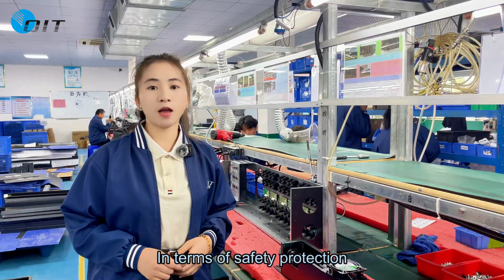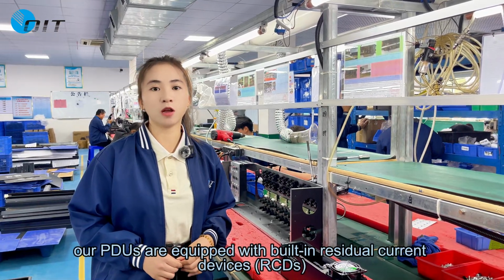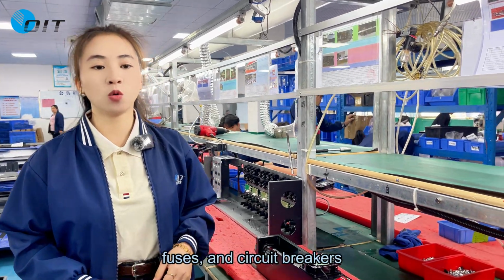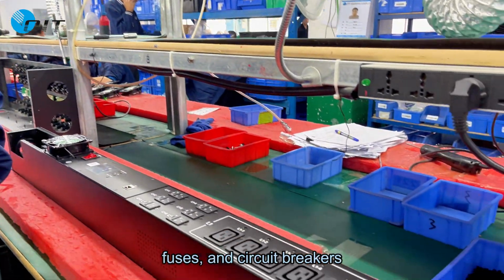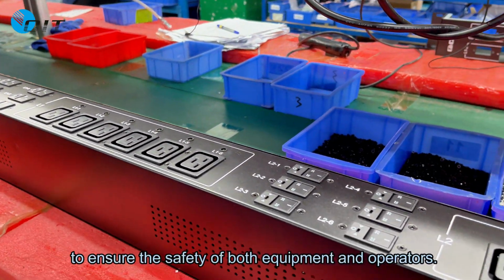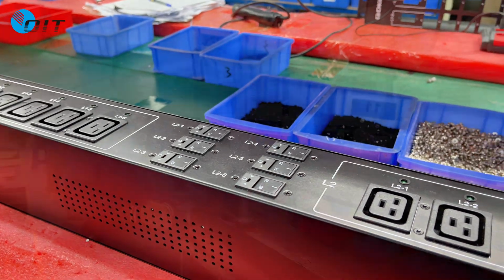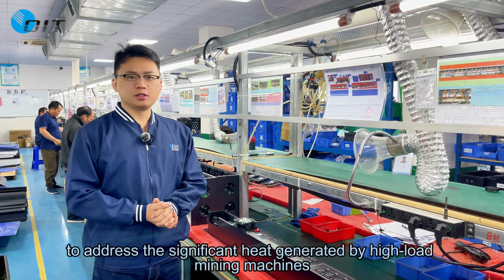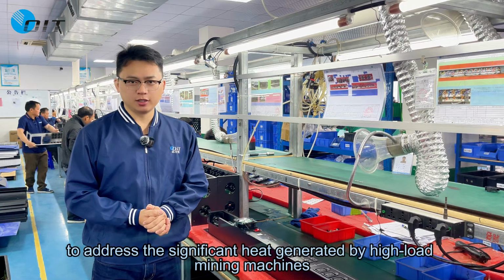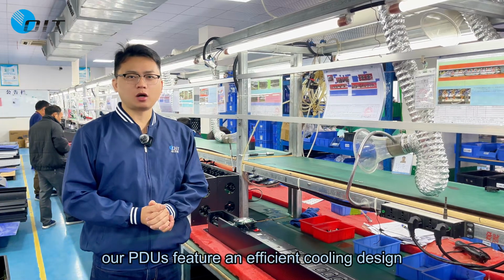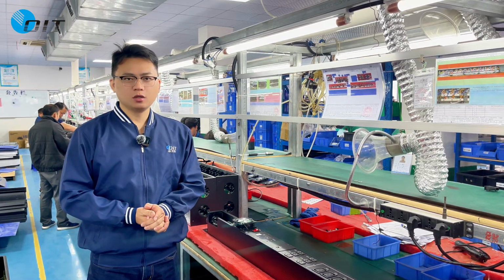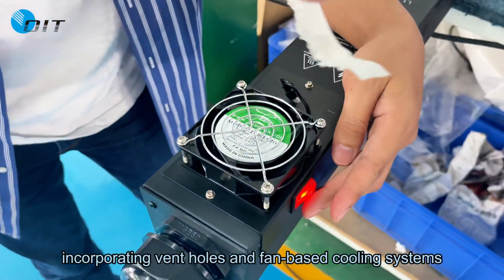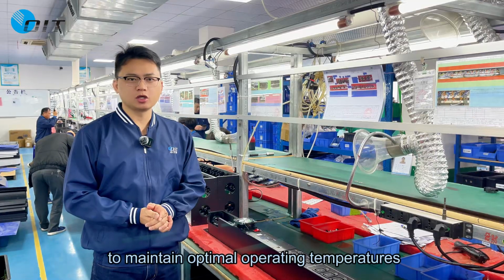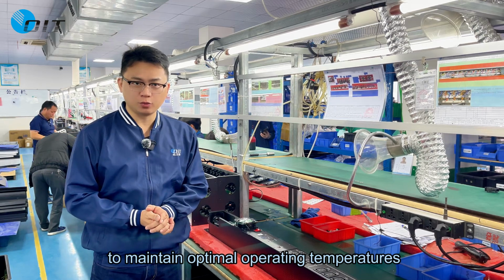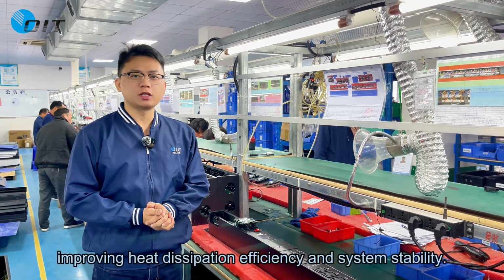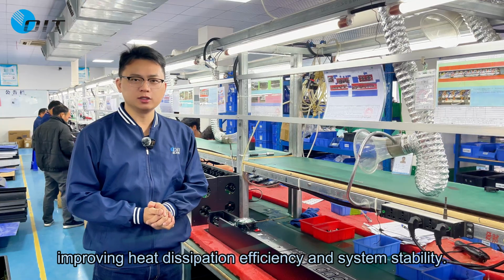In terms of safety protection, our PDUs are equipped with built-in residual current devices (RCDs), fuses, and circuit breakers to ensure the safety of both equipment and operators. Lastly, to address the significant heat generated by high-load mining machines, our PDUs feature an efficient cooling design, incorporating vent holes and fan-based cooling systems to maintain optimal operating temperatures, improving heat dissipation efficiency and system stability.